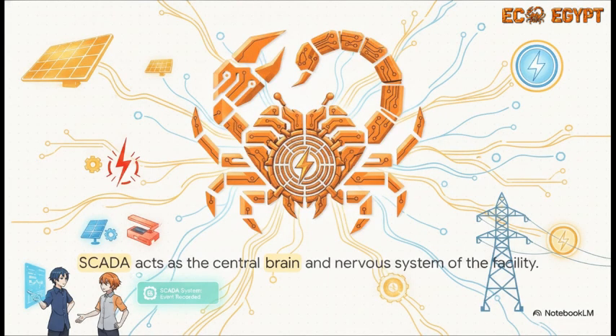Just like a biological nervous system, these control hubs are pulling together millions of data points to keep the plant alive, safe, and perfectly synchronized with the utility grid. If a short circuit happens in the MV network, the protection relay detects it instantly. The circuit breakers trip to isolate the damage, and the SCADA system logs the event, all while allowing the rest of the healthy loops in the plant to just keep pumping power right to the grid.